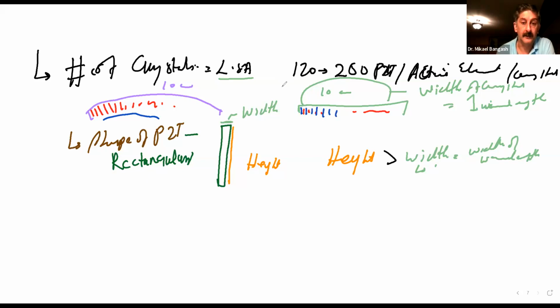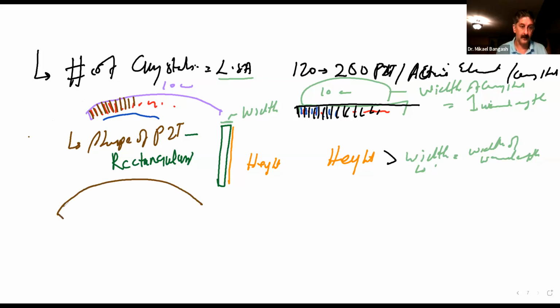But the difference between these two is that in your linear sequential array, the crystals are lined up in a straight line because of the straight footprint. Whereas in your curved, or curvilinear, or convex array transducer, they're still lined up side by side, but more or less along that curved footprint.